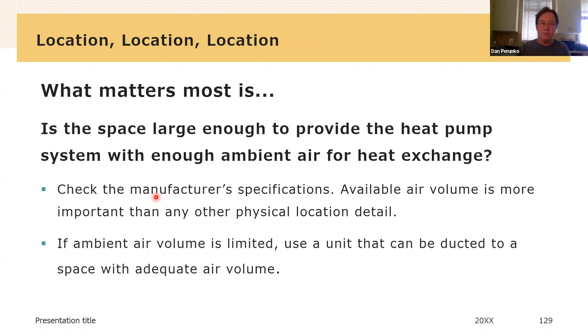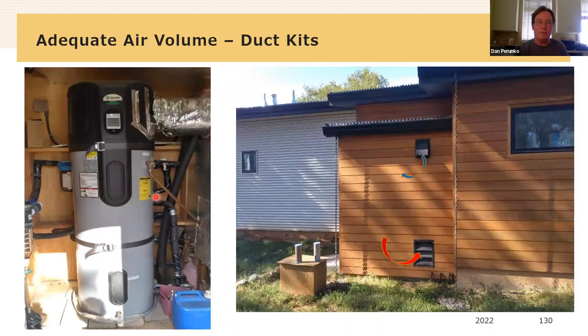So, I've said this a few times: if you starve the heat pump for available heat, then it will fail. It needs to have enough available heat in the air around it. And you have some workaround strategies like this, where this particular system intakes air here and exhausts it there, so the cold air exhausts through that vent, and new warm air comes in through this vent. So it's changing the air in its little mechanical space while it's working.